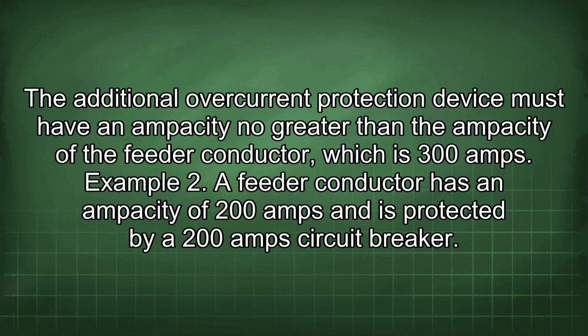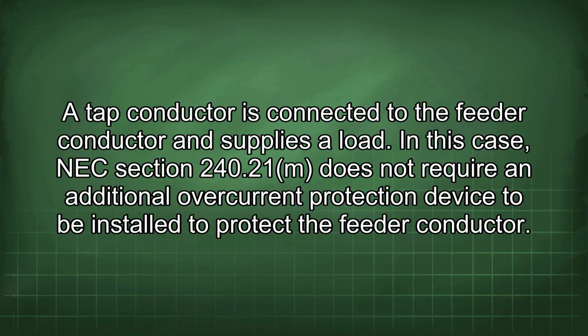Example 2. A feeder conductor has an ampacity of 200 amps and is protected by a 200 amp circuit breaker. A tap conductor is connected to the feeder conductor and supplies a load. In this case, NEC Section 240.21 does not require an additional overcurrent protection device to be installed to protect the feeder conductor.